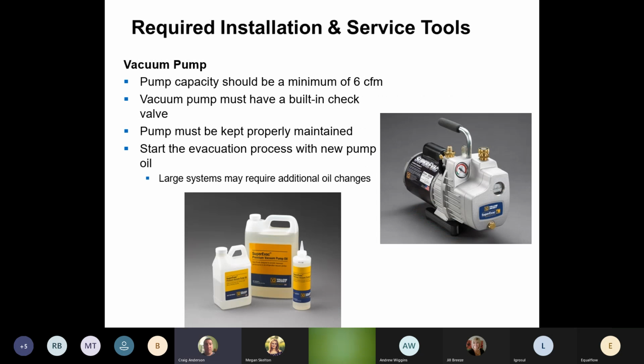Vacuum pumps, big thing also. Make sure your vacuum pump has been serviced. I know some of the branches actually do vacuum pump days. It's great. You bring it in, they change the oil for you. Minimum 6 CFMs. Let's not get too big on a vacuum pump on a system. We can create problems that way if we're pulling the vacuum down too quick. If we're pulling a vacuum down too quick, we could actually make the inside of the copper freeze with the moisture that's in there because we're drying it down too quick. Once you draw it down, you turn it off, then that frozen moisture unfreezes and we get contamination in our gauges. So be mindful, nice low vacuums, 6 CFMs, sorry.